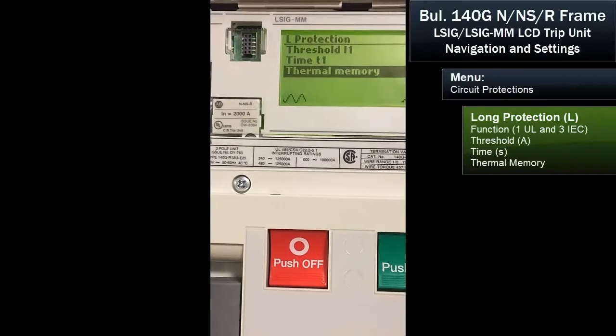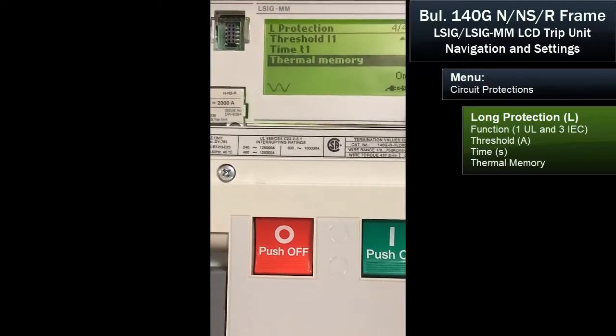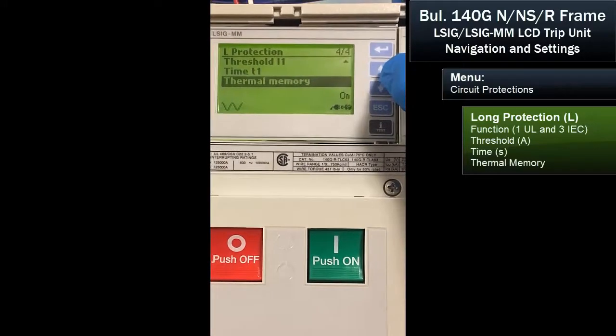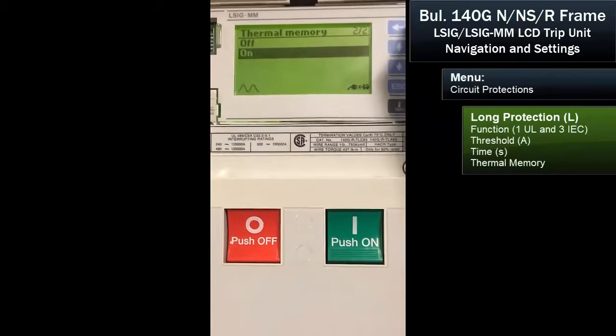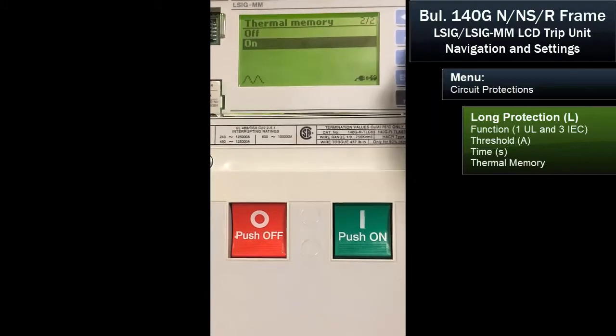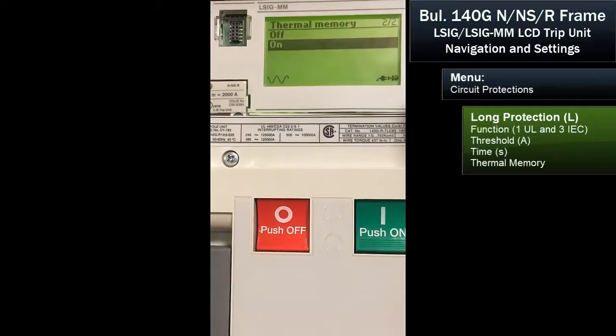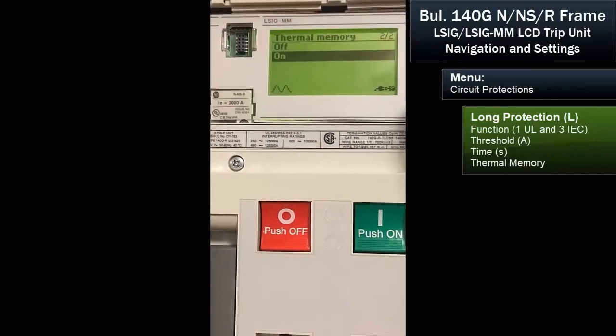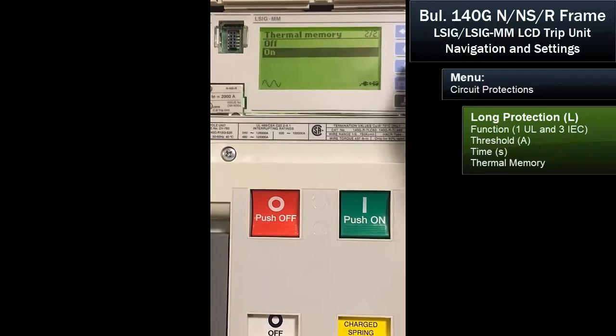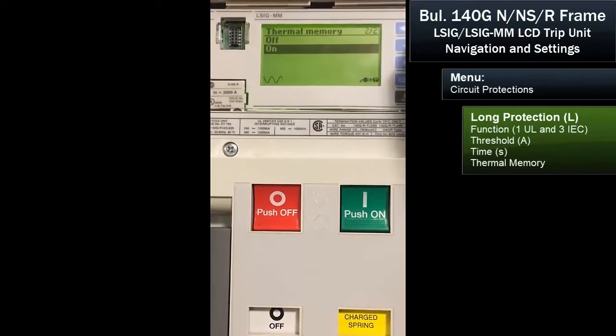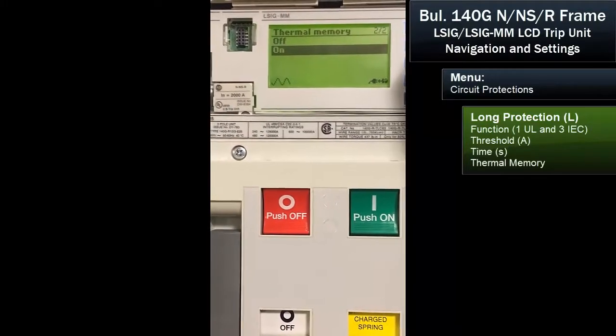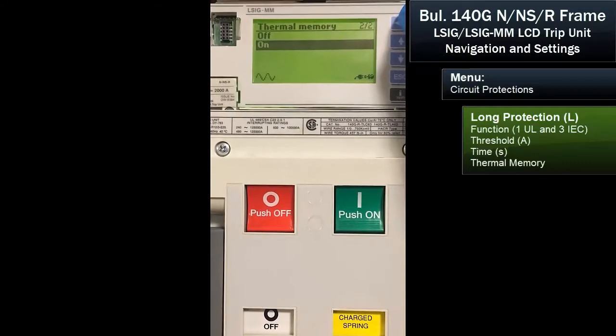Next, we'll set the thermal memory. This is showing it's turned on, but I'll just confirm that using the arrow button. We have the choice of thermal protection on or off. UL will require in November of 2021 that all electronic trip units have thermal memory, and it won't be an option. So we suggest leaving this on.